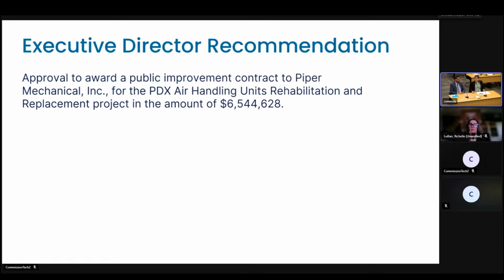We're replacing the electronics that drive those fans, the variable frequency drives. We're replacing cooling coils that have fouled and been damaged over the years, and in order to gain heat transfer efficiency, you want to replace the coils. Another major component is the controls: the microprocessors, and physical devices like dampers that vary the flow and mix of air between outside air and return air. Those are some of the major points of refurbishment, but there are some other things, door seals, some really mundane things that we're doing.